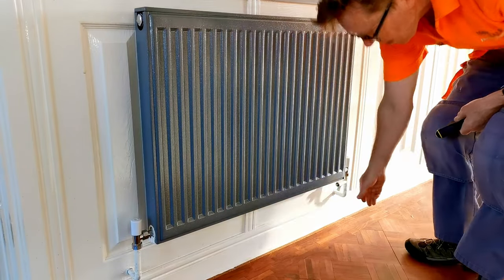Not all lock shield valves are the same - some need a screwdriver to adjust. As your house heats up it becomes harder to balance the system and more difficult to tell the difference between the two pipe temperatures. That's why we always want to balance the system when the radiators are cold and your house must be cold - you can't do this on a summer's day. To get the best results, balance your system over several days. Do it the first day until the system warms up, then come back the next day and do the same again, going around the system until you get the right flow and return temperature difference. That way you'll get your boiler working at its most efficient and reduce your gas bill.